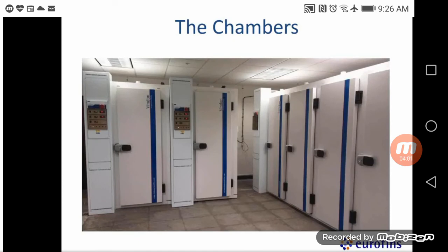And what's going on in these pieces of equipment is these chambers have a unit behind them that you can't see in this picture, but what it's doing is it's taking water and it's warming or cooling the water to flow through a piping system within the unit, so that it's a very consistent temperature regulation, where in older units what you would see is it would be forced air and it could cause spikes in the temperature regulation.